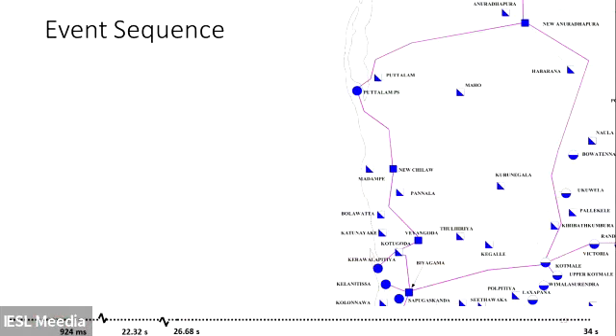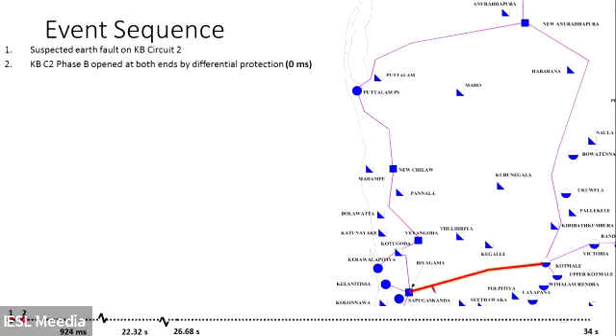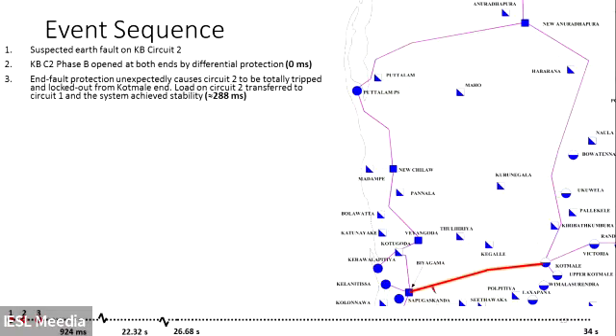Then if I summarize the sequence of events: a suspected earth fault on the Kothmale-Biagama circuit 2, then circuit 2 phase B opened on both ends by the differential protection, which I take as the 0 millisecond. Then end-fault protection unexpectedly caused circuit 2 to be totally tripped and locked out from the Kothmale end. Simultaneously the load on circuit 2 transferred to circuit 1, and the system achieved stability in nearly 288 milliseconds. This is exactly the time at which the neutral current came down in the other line. Then the Kothmale-Biagama circuit 2 phase B auto reclosure operated after less than 1 second.